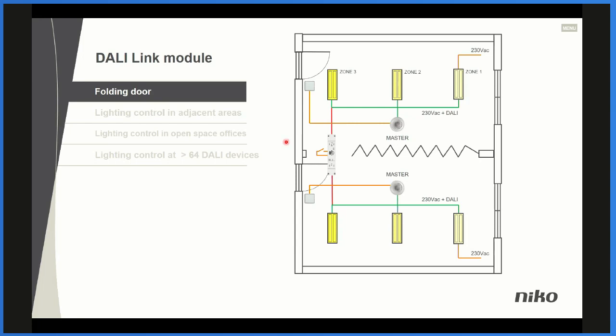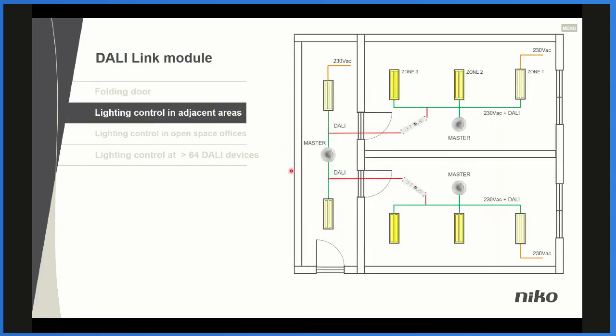The same we can do if you have, for example, adjacent areas: an office here and an office here, and a corridor here. If there's somebody present in these offices, this office or another office, there will be some light in the corridor. That means by adjusting the DALI module, you can decide the light level in the corridor if there's still somebody present. And by the end of the day, when they have left all the offices, the light in the corridor will automatically switch off in order to have no power consumption and higher comfort.